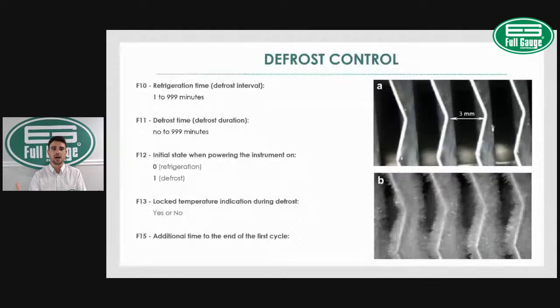Coolers are running fine. Whenever a power failure happens, all the coolers will come back on at the same time and will perform the 6 hours and will enter defrost at the same time. And that will create an electricity peak. We want to avoid that. And in order to avoid that, you can set individual times. You can set different times on F15 for every piece of equipment. So that way, your next defrost cycles won't be synchronized.